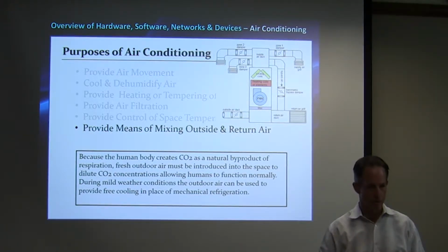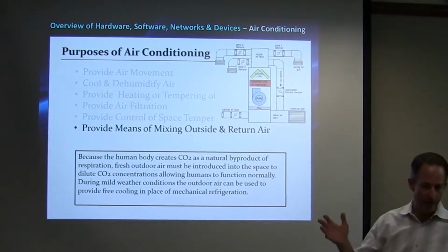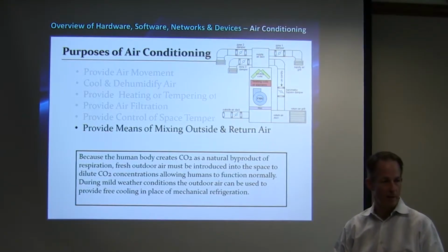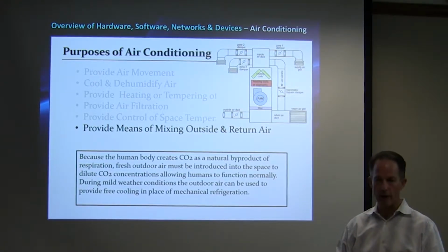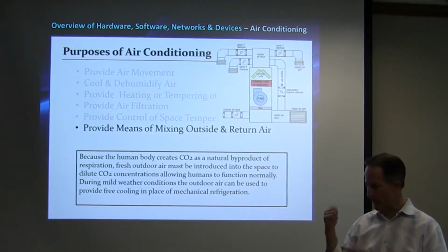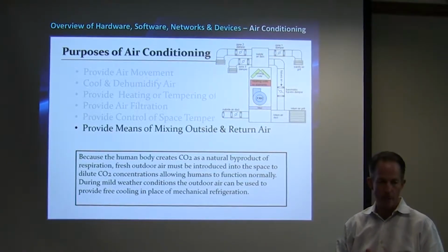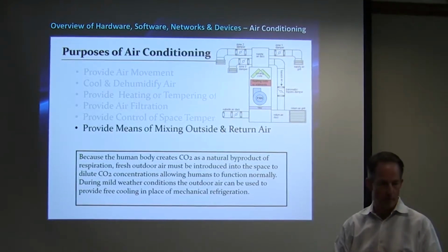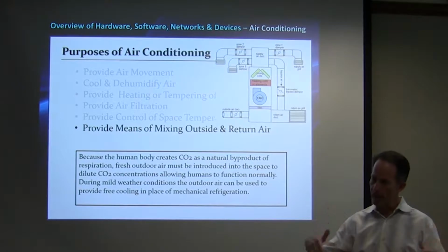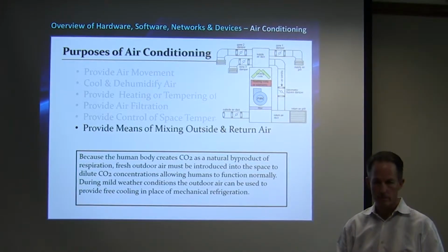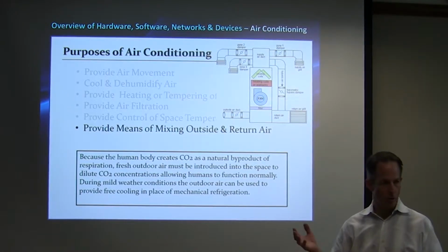That's the lowest level of CO2 concentrations out in the ocean. Here in Salt Lake Valley, on a good day, we're maybe 440, 450, maybe 430-ish. We're not that far above that if we've got really good air. If we're getting lots of particulates, fires, stuff like that, then it definitely goes up. In any given room, like say this room, we've got maybe 15 people in here. What would you guess our CO2 would be in here if we have air moving in and out? 600-700. Yeah, we could be in the 600-700 range pretty easily with just a small group of people.